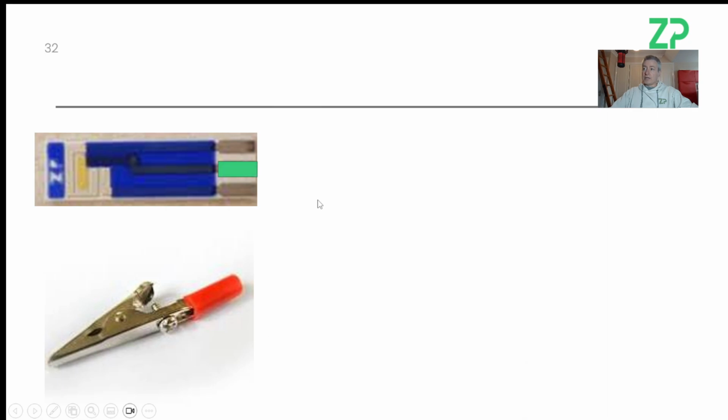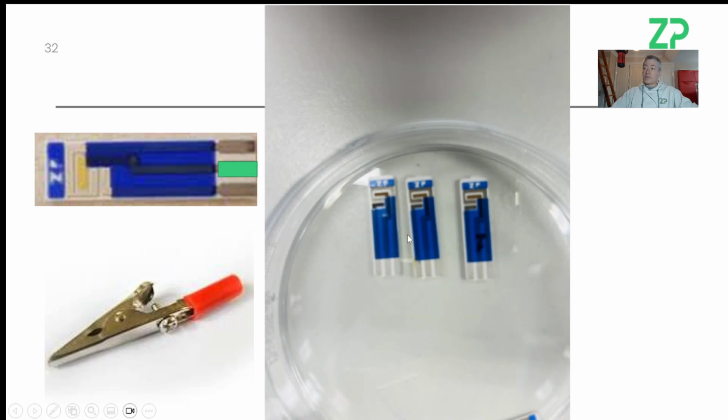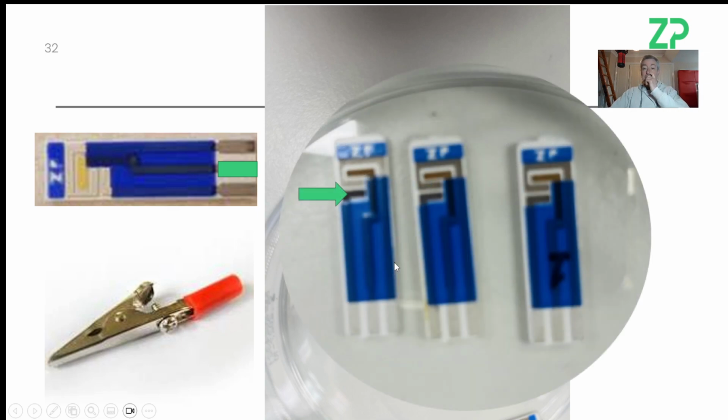So you're trying to clip onto there. And I can tell from your photos that the way you've set this up, that counter electrode should not in any way be in the circuit, but it's so darkened, it's clearly been, I think you're clipping onto the working and also catching the counter as well.